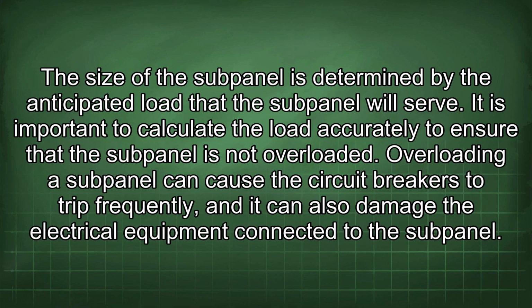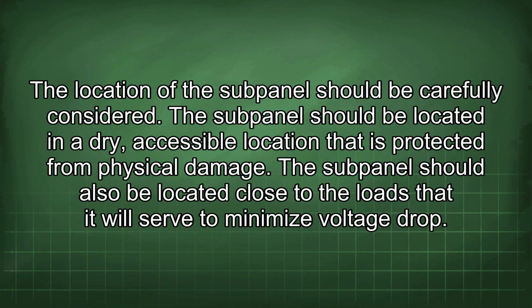The size of the subpanel is determined by the anticipated load that the subpanel will serve. It is important to calculate the load accurately to ensure that the subpanel is not overloaded. Overloading a subpanel can cause the circuit breakers to trip frequently, and it can also damage the electrical equipment connected to the subpanel. The location of the subpanel should be carefully considered.